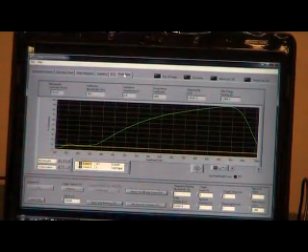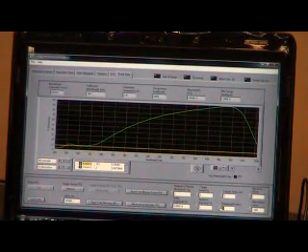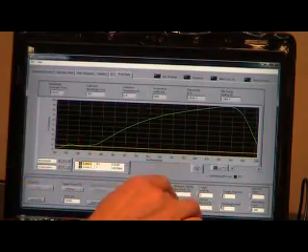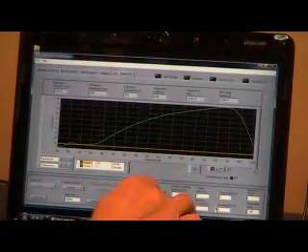Now you notice it says our user wavelength down here is 0. That's because this is the first time this software has been loaded on this machine. I can change that to 1047. And our correction factor immediately jumped to unity. Now the software will remember all of these controls and settings when you exit. The first time you power the software up on a new machine, that configuration file isn't present, so it defaults.